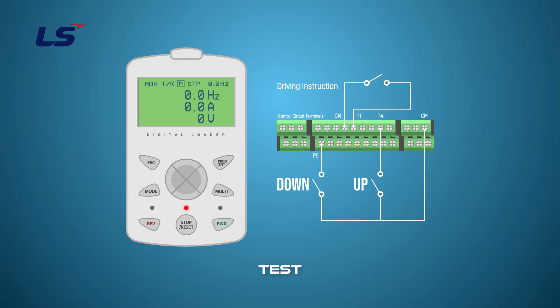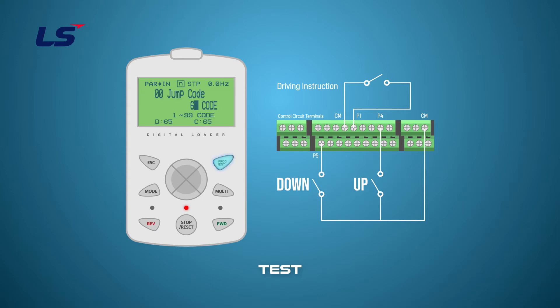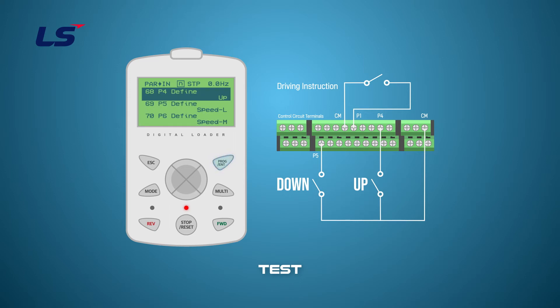Now, let's test the Up-Down in Normal mode. After selecting the digital input to use for Up-Down operation, program the corresponding terminal function to 17 Up or 18 Down.